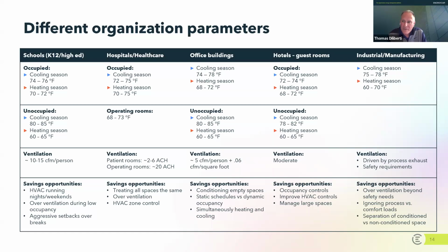My advice is to understand what your systems do and set these numbers at reasonable levels. Over time, as you know your systems and occupancy better, I'd encourage you to more aggressively pursue these set points, because every couple degrees lower or higher during cooling season brings savings. Step up or down a little at a time, but there are definitely opportunities there.